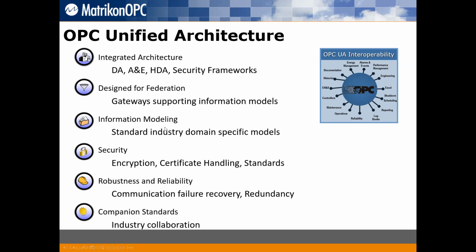So the main advantage of the OPC UA is that it's not attached to Windows anymore, which means that the security is different. We don't use Windows users anymore. We don't need to configure permissions for the Windows users that are executing the applications. Normally, the security is based on digital certificates. You need to exchange digital certificates between the two applications.